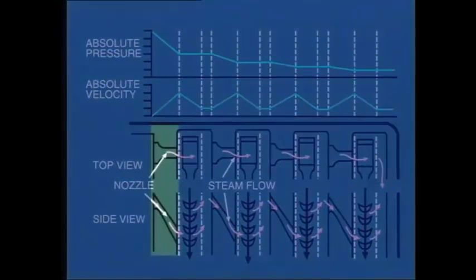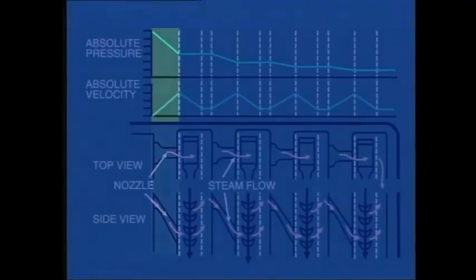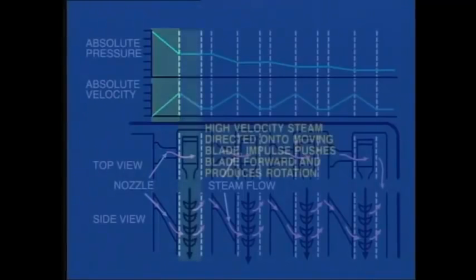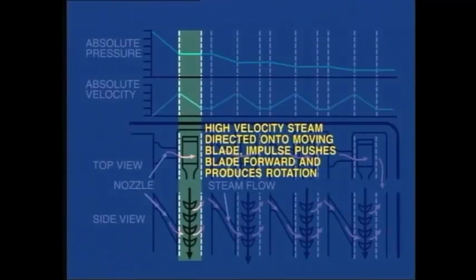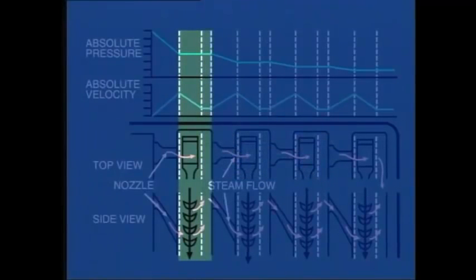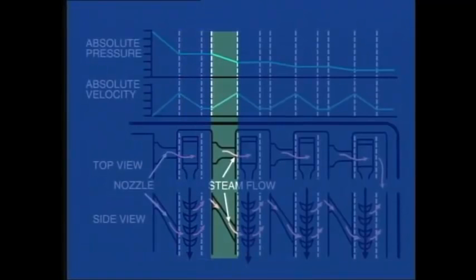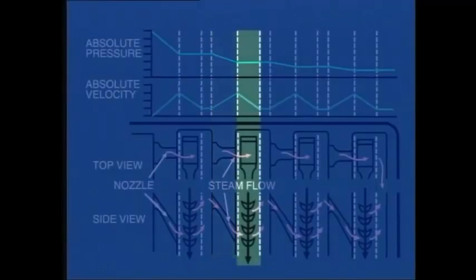Let's first examine impulse blading. As the steam passes through the first row of stationary blades or nozzles, its pressure decreases, and as a result, the steam velocity increases. These changes are plotted on this graph. As this high-velocity steam is directed onto the moving blade, the impulse pushes the blade forward and consequently produces rotation of the shaft. By the time the steam leaves the moving blade, it has lost much of its velocity, and it then passes on through the next row of stationary blades. Again, the pressure falls and the velocity increases due to expansion of the steam, and once again this is directed onto the next row of moving blades, and so on.